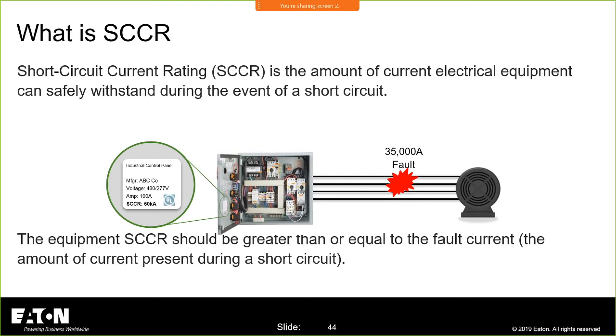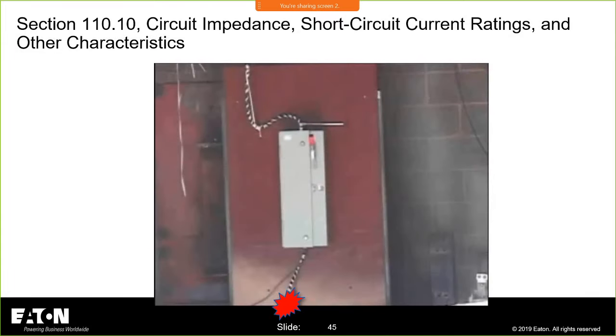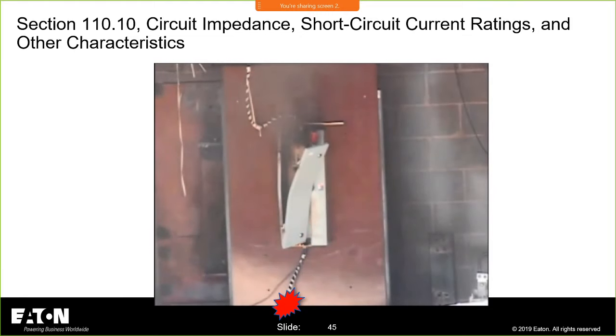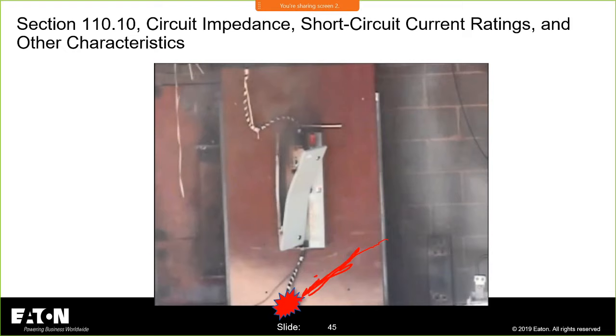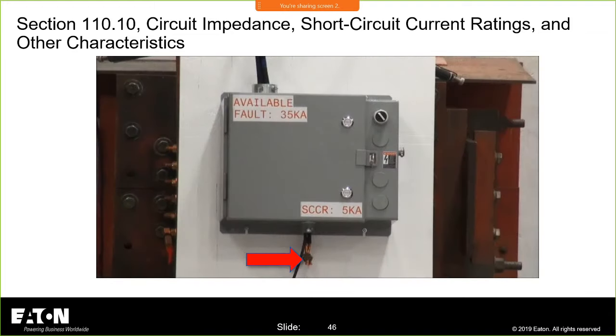Circuit breakers have an interrupting rating. They don't have a short circuit current rating. Electrical equipment, distribution equipment like this, will have a short circuit current rating. And this is what happens when you exceed the short circuit current rating. The fault is actually down here, not inside that equipment, but this equipment saw more current than what it is rated to handle from a short circuit current rating perspective. And you let the smoke out.